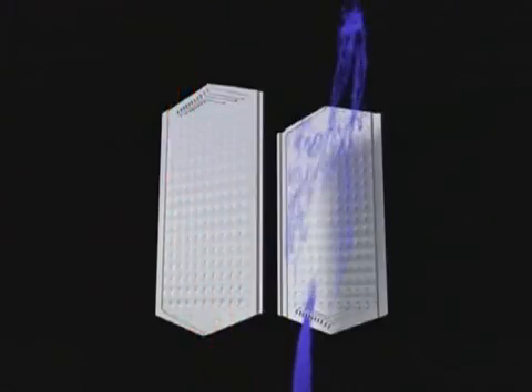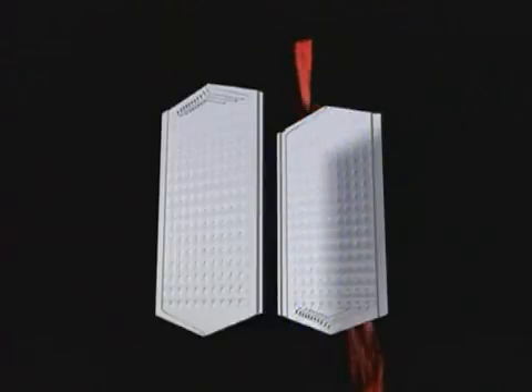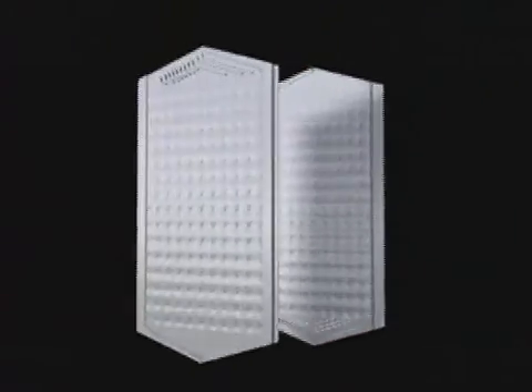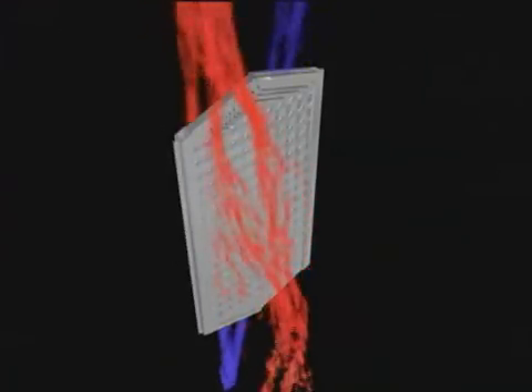After entering, the gases are spread out over the entire plate by internal turning vanes. The gas streams converge again at the opposite end of the plate and exit on the opposite side to their entry point. This crossover effect prevents the streams from bypassing a large amount of the surface. Individual plates are automatically welded together to form plate pairs.